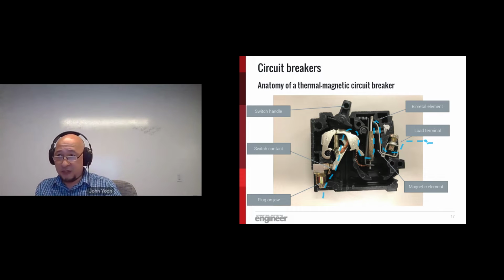So this is a picture of what we just described. We have the bimetal element that handles the overload side of it. We have a magnetic element that handles that short circuit part of the equation. And like they say, a picture is worth 1,000 words. Hopefully this makes things a little bit clearer. And when you think about it, it's almost like a mousetrap. Once you trip that latch, the spring will draw the circuit breaker open. And either the magnetic element or the bimetal element can trip that latch.